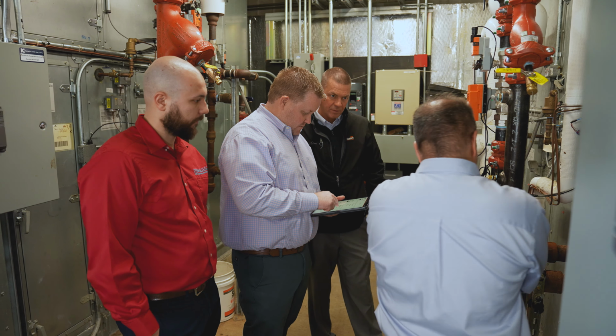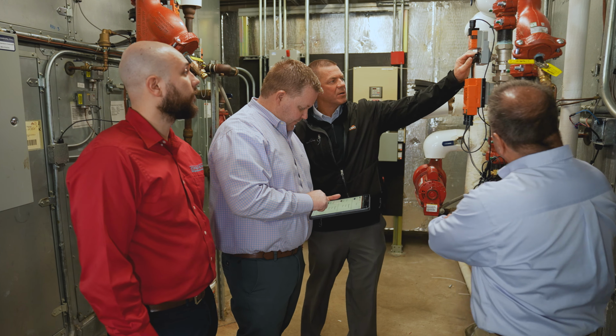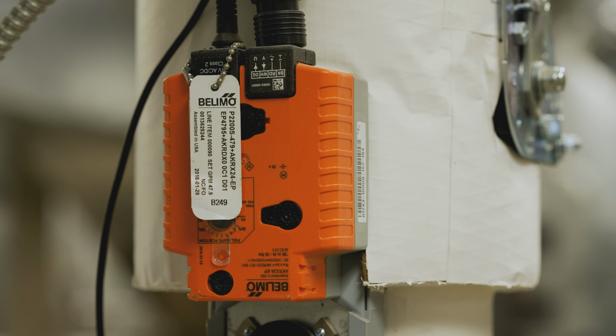Increasing the delta T back to the central plant and the chiller greatly increases the chiller performance by putting it in its peak efficiency curve.